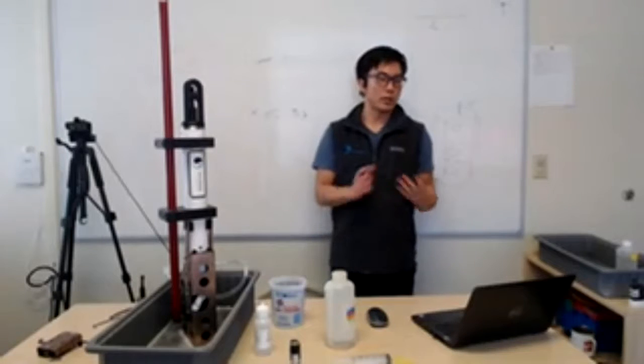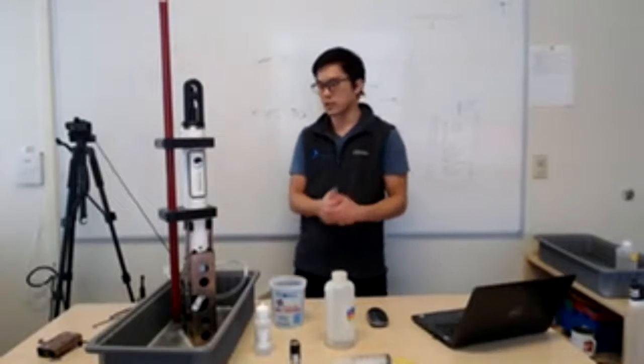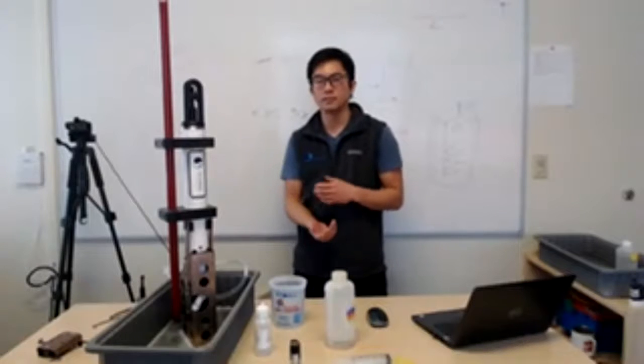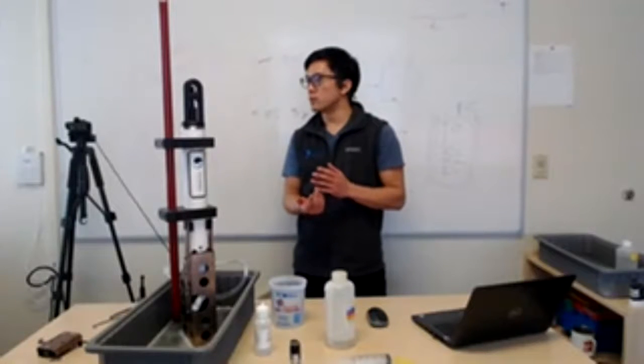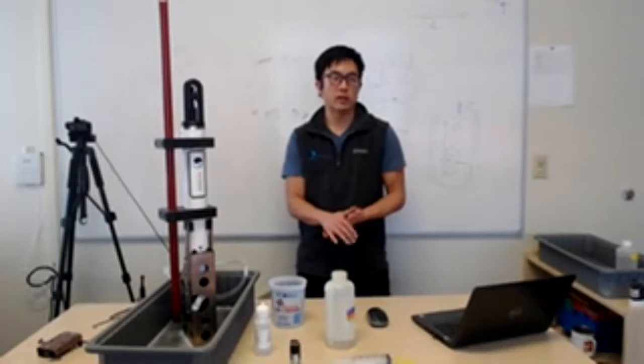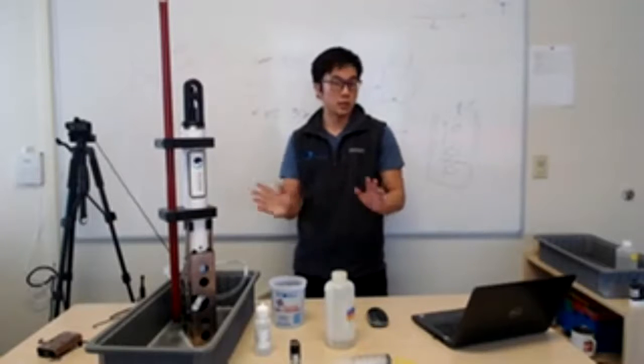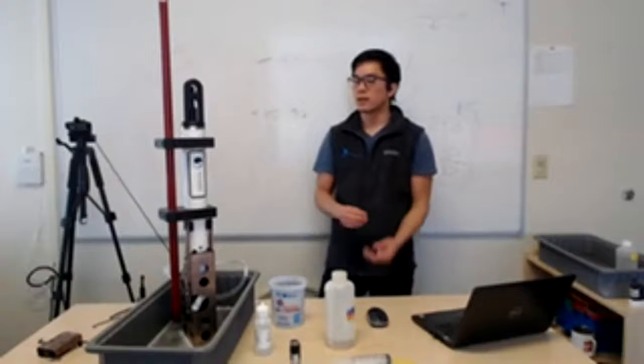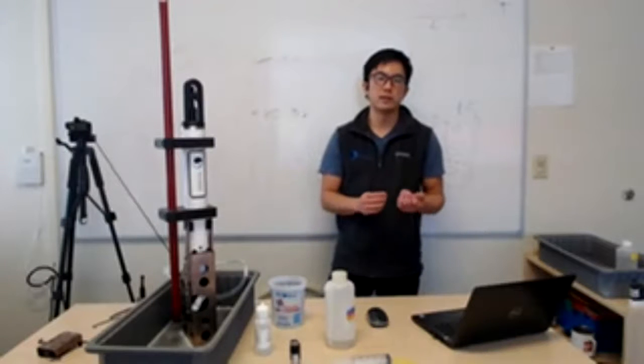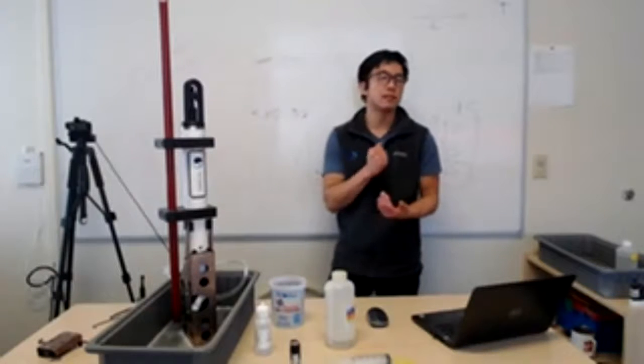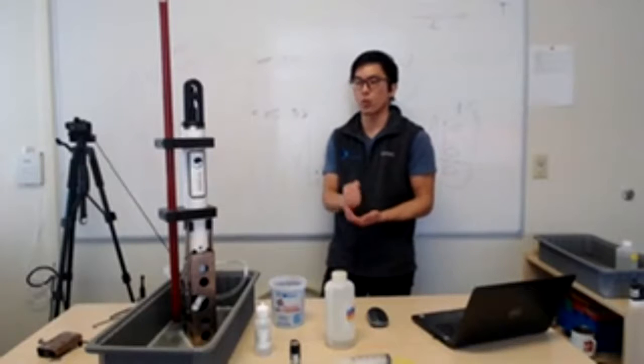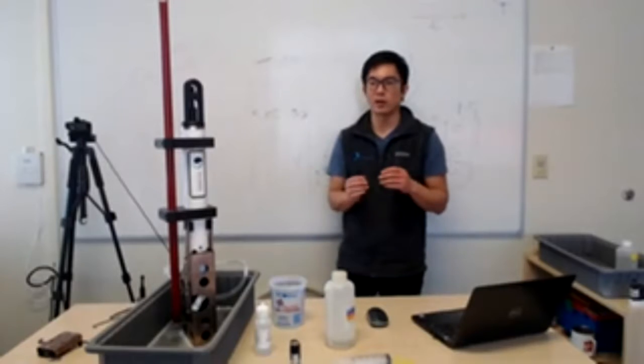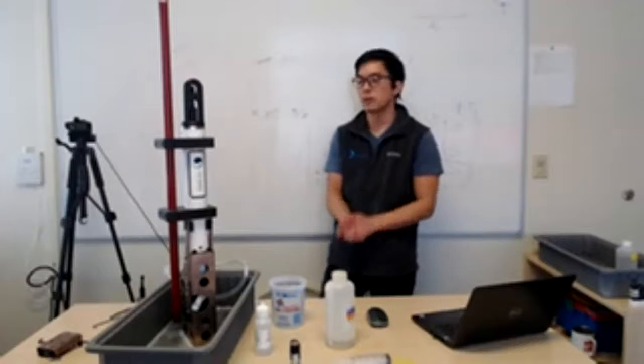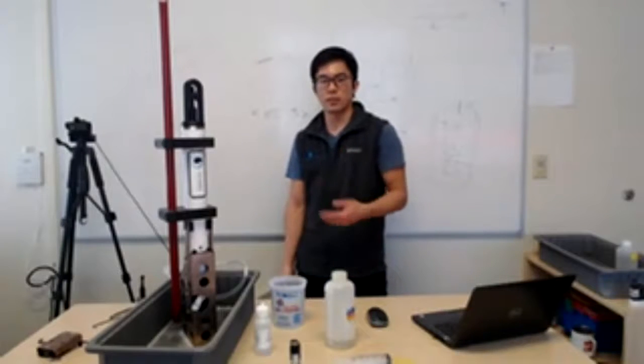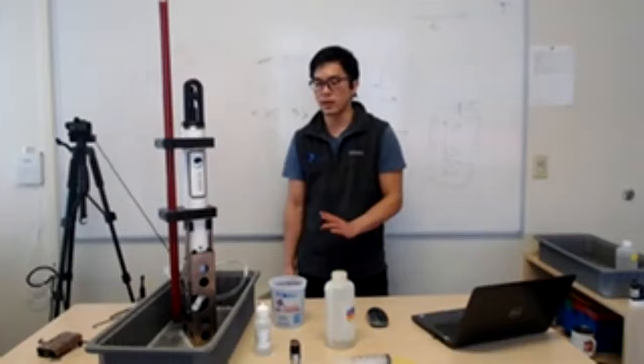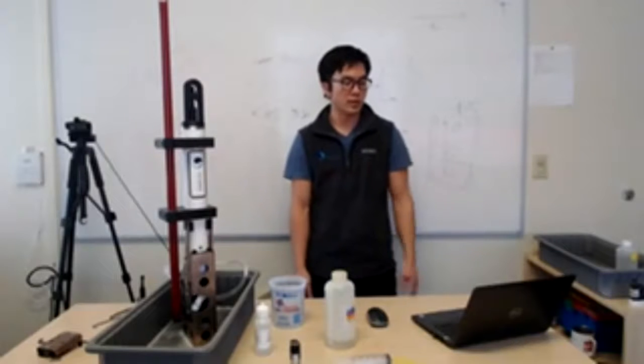What we do here in some of our test baths, not our calibration baths, is we will take the volume of water in the test bath and then calculate how much salt we need to add to that. It's usually an enormous amount of salt. And then that's a good way for us to just quickly say, is the conductivity sensor on this instrument working? We expect this to be around 30 PSU or something. So we can put the instrument into that bath with a bunch of dissolved table salt, and then sure enough, it'll usually tell us 30 PSU.